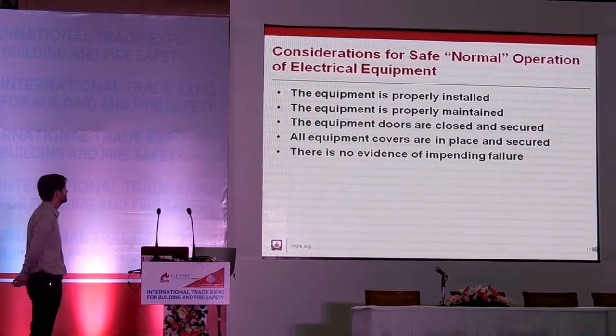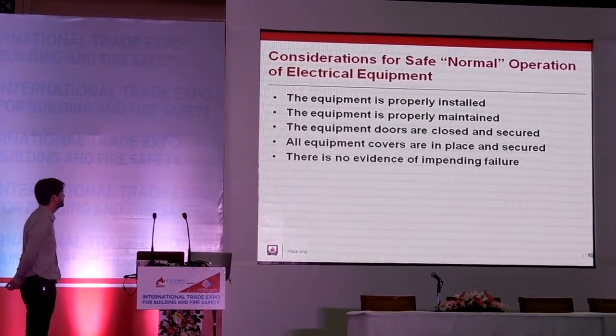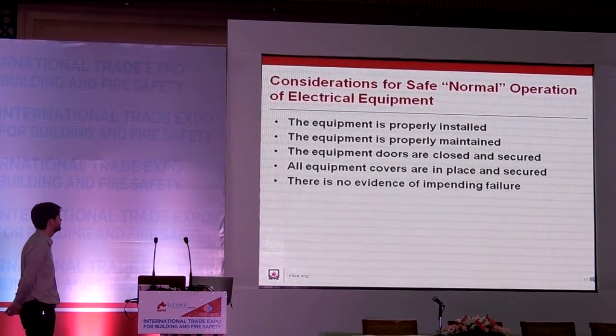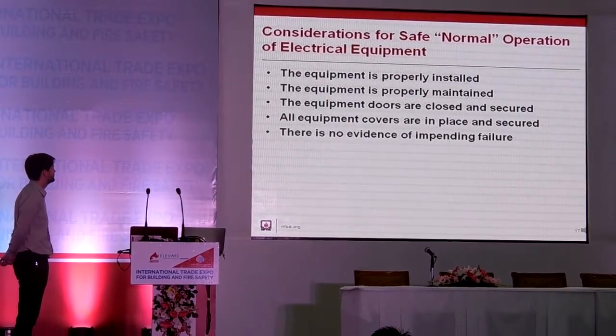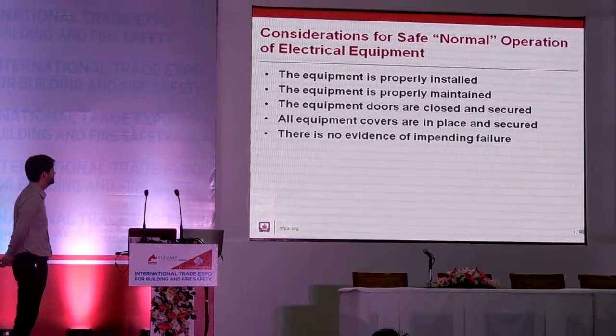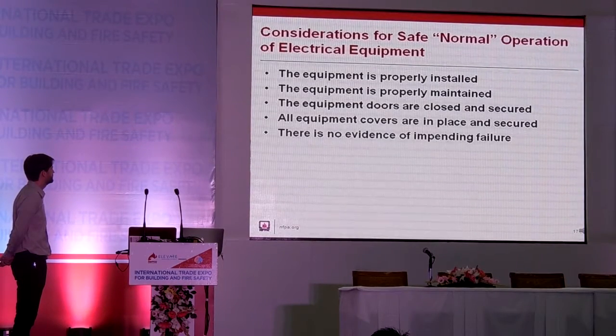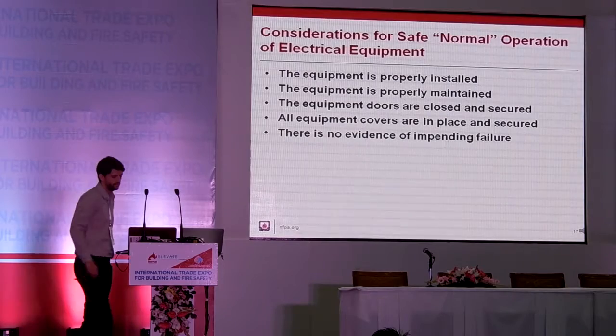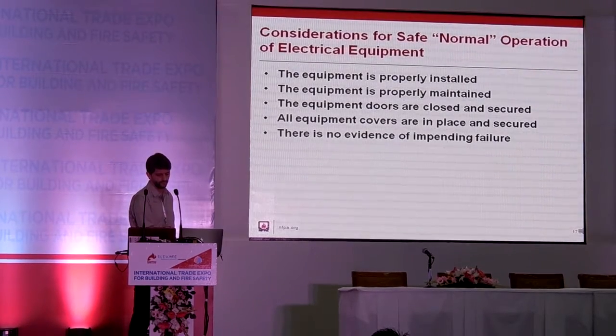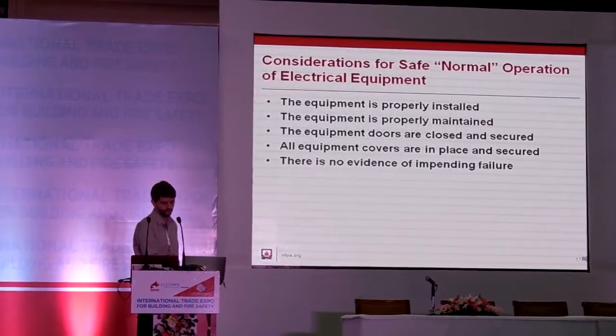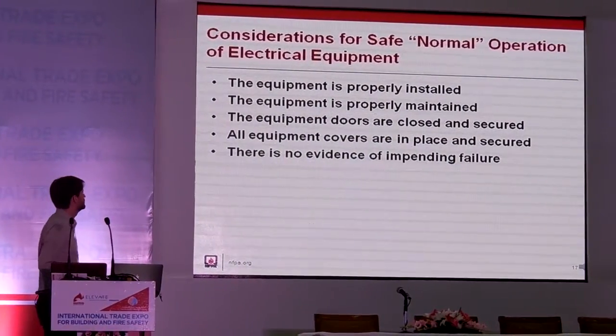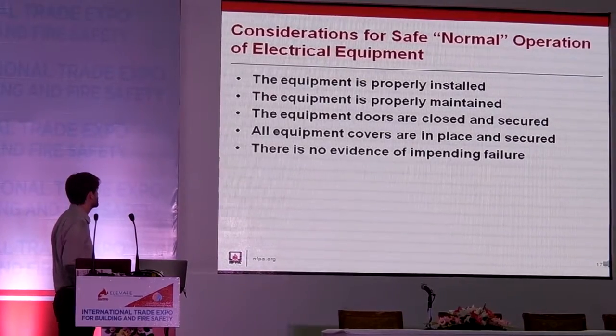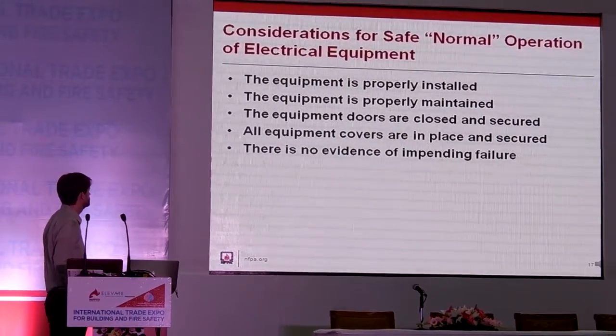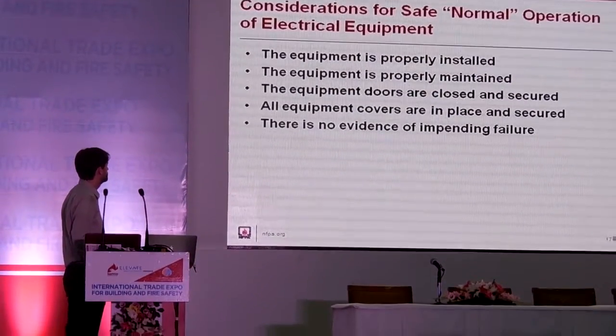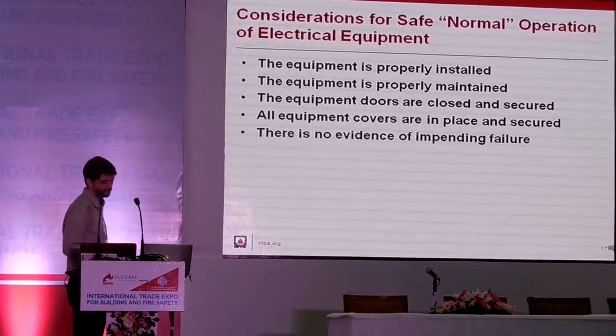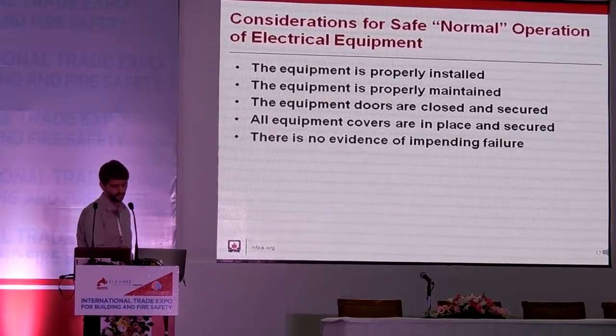Other equipment covers need to be in place and secured to prevent accidental contact with energized parts that are within the equipment, as well as to contain and reduce the effects of equipment failure. And then finally, electrical equipment that has been in service for a number of years has been exposed to severe operating conditions. Those are factors that need to be looked at to ensure whether the equipment is subject to impending failure. Are there telltale signs such as corrosion on the equipment?